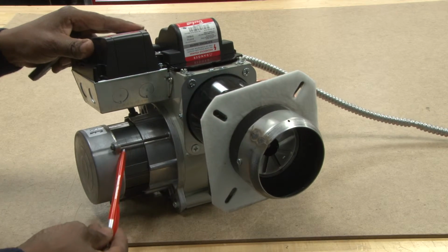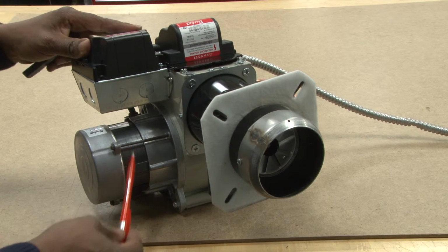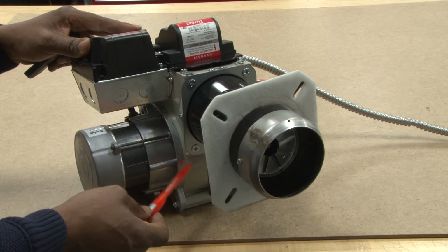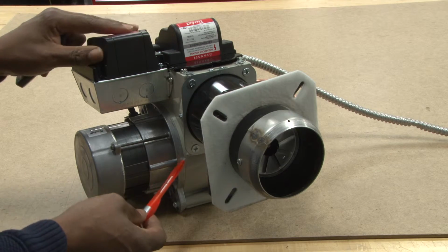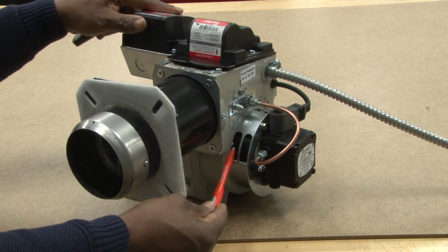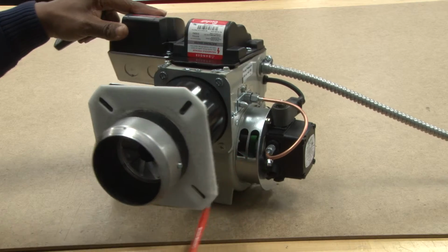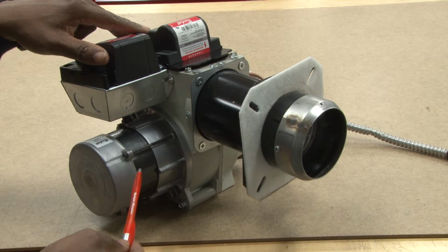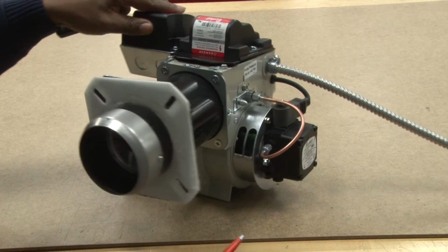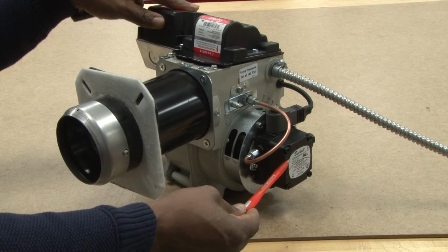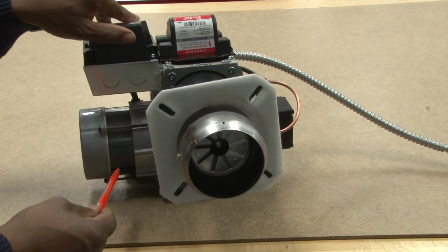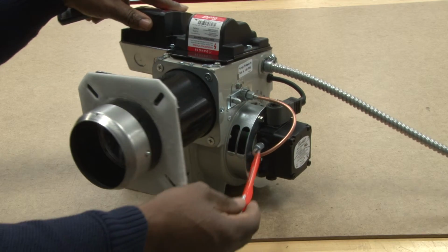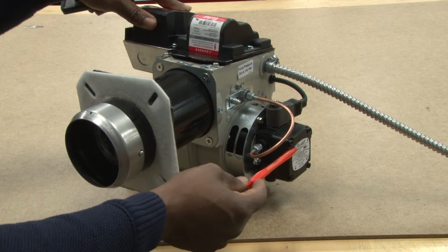This portion is the motor, which drives the blower on the inside of the blower assembly. Inside the blower assembly is a blower wheel, which pulls air in through the shutters you see here. The motor is driving the blower wheel, but this same motor is also driving the oil pump through a coupler. So that one motor on this side drives the blower wheel on the inside, but also the oil pump.